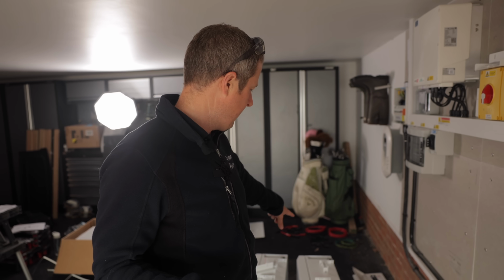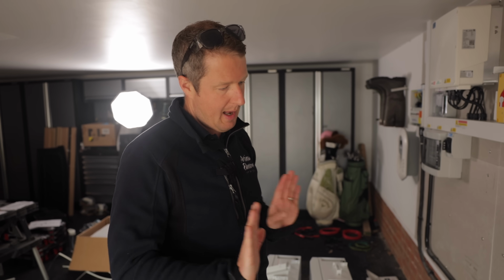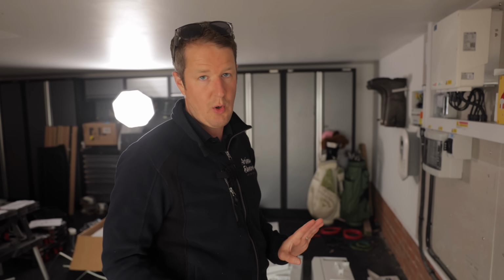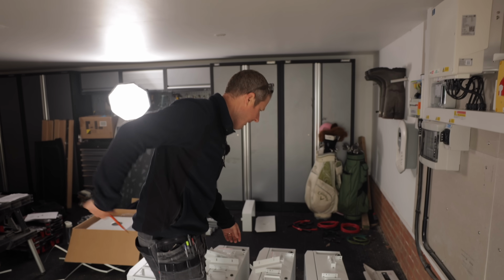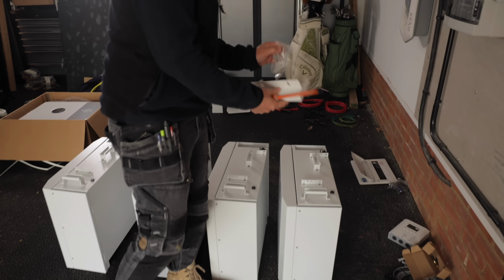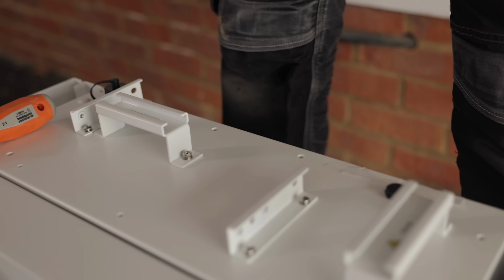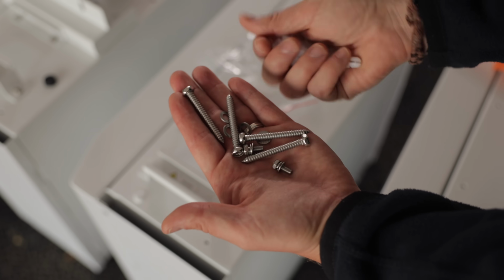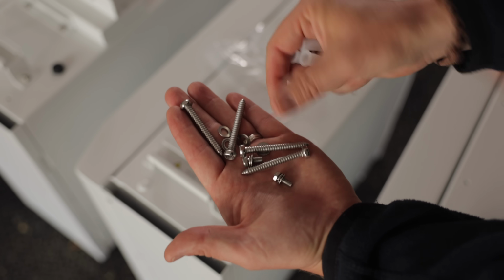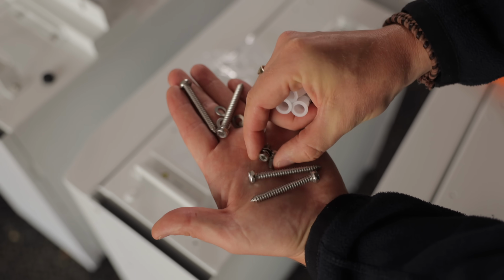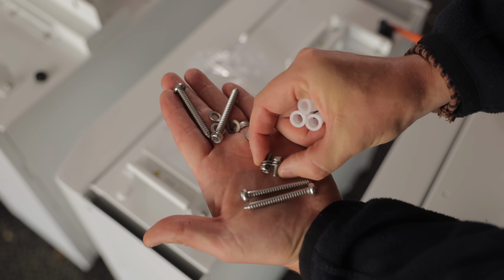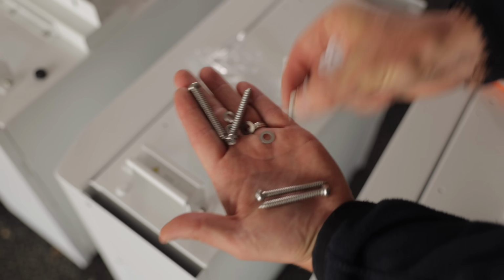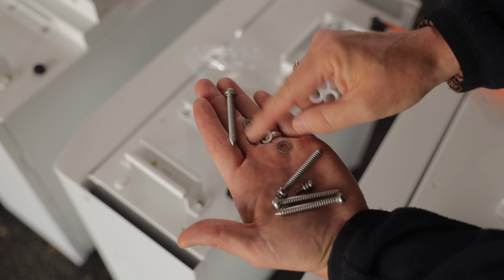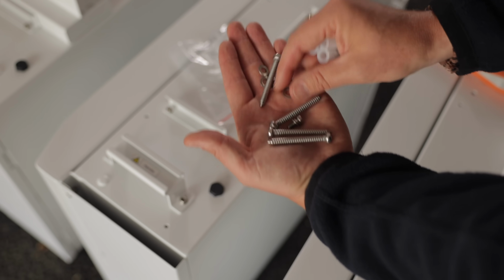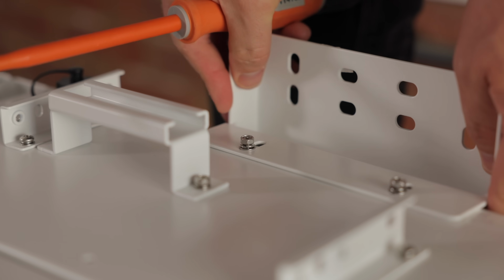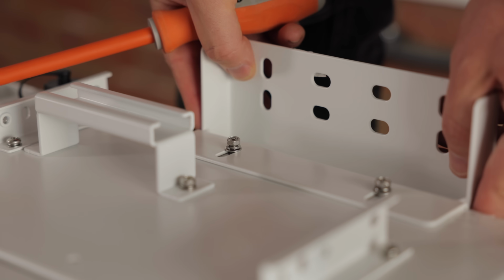We need to get the first battery module on and sit it against the wall to make sure it all fits correctly. To do that we've got to attach the wall mounting bracket to the battery module. Each battery module comes with 4 fixing screws, 4 raw plugs, and 2 screws like this to fix this bracket down, plus 4 washers for the fixing screws. We'll connect this on loosely so it can be slid back to match the wall level.